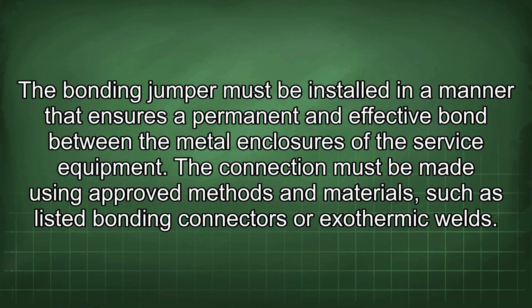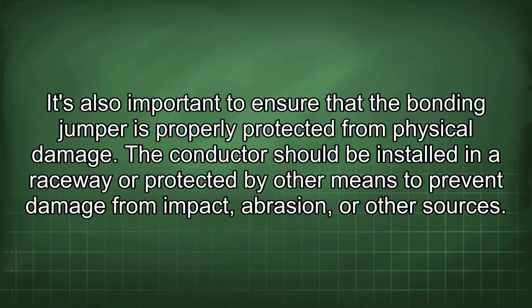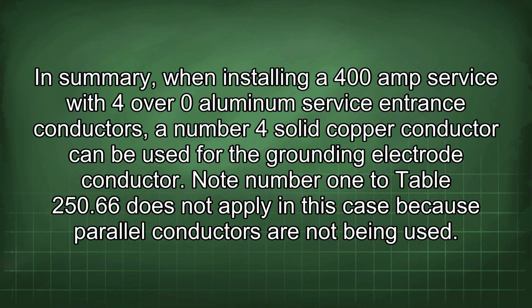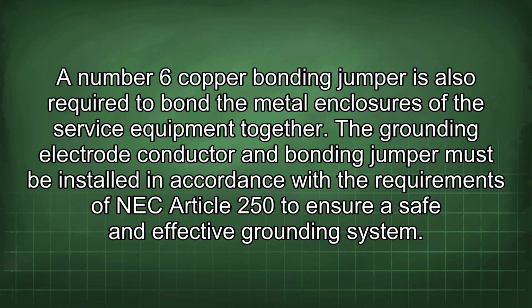The connection must be made using approved methods and materials such as listed bonding connectors or exothermic welds. It's also important to ensure that the bonding jumper is properly protected from physical damage. The conductor should be installed in a raceway or protected by other means to prevent damage from impact, abrasion, or other sources. In summary, when installing a 400 amp service with 4/0 aluminum service entrance conductors, a number 4 solid copper conductor can be used for the grounding electrode conductor. Note number 1 to Table 250.66 does not apply in this case because parallel conductors are not being used. A number 6 copper bonding jumper is also required to bond the metal enclosures of the service equipment together.